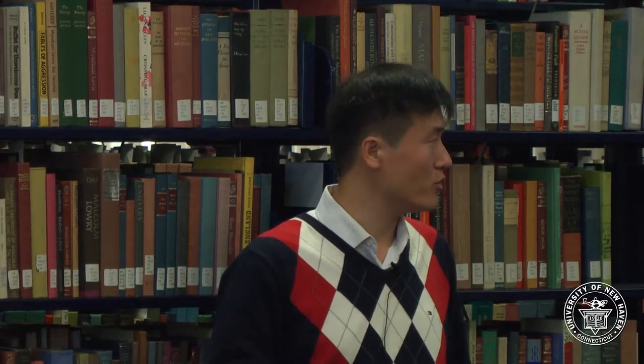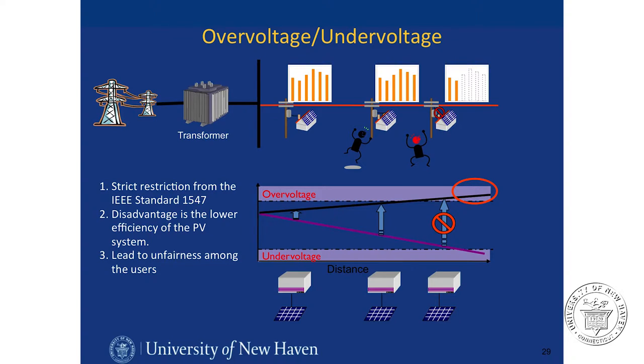If the actual generation is too large, it will boost up the voltage at the remote end and cause overvoltage issues, which should also be avoided in the distribution network. Based on the industry standard, once overvoltage happens, the PV panel close to the point causing the overvoltage must be shut down. This will cause certain areas to have PV panels shut down, leading to unfairness among PV users and discouraging their participation in installing renewable energy. This is the overvoltage and undervoltage issue in the distribution network caused by PV panels.